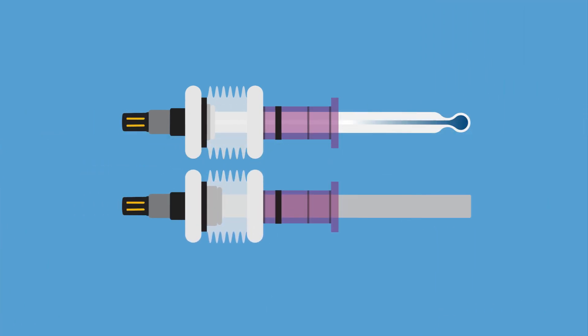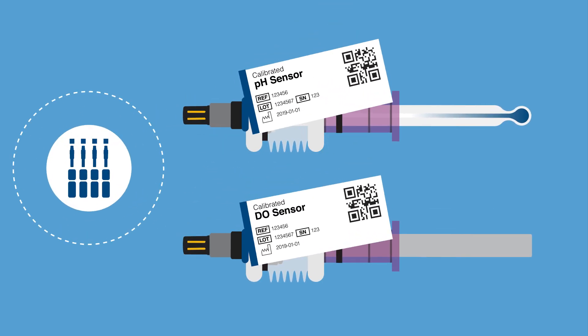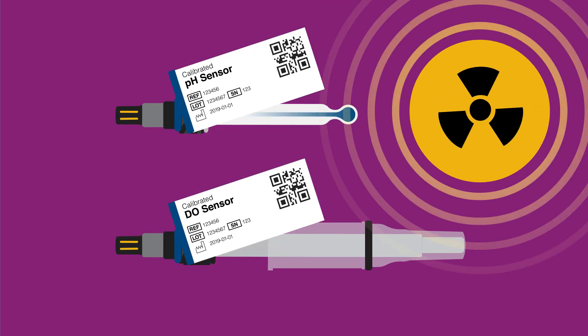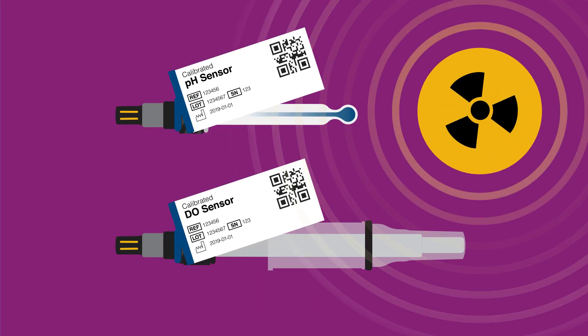Ideally, process sensors should be specifically designed for single-use environments. This would mean sensors that are pre-calibrated, pre-installed without insertion devices, and pre-sterilized by gamma radiation.